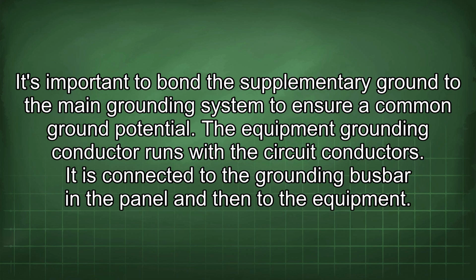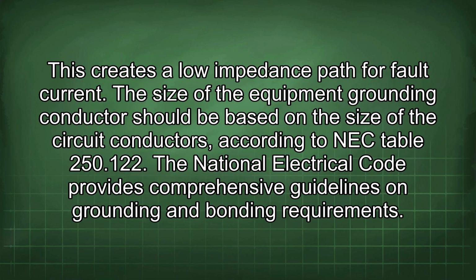The equipment grounding conductor runs with the circuit conductors. It is connected to the grounding busbar in the panel and then to the equipment. This creates a low impedance path for fault current. The size of the equipment grounding conductor should be based on the size of the circuit conductors according to NEC Table 250.122. The National Electrical Code provides comprehensive guidelines on grounding and bonding requirements.